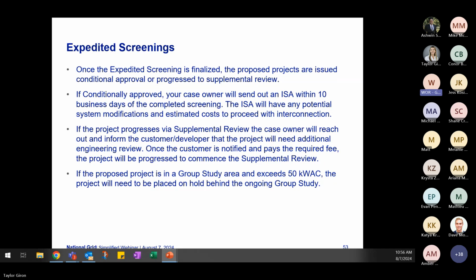Once the expedited screening is finalized, proposed projects are issued conditional approval or progressed to supplemental review. If conditionally approved, your case owner will send out an ISA within 10 business days of the completed screening, including any potential system modifications and estimated costs to proceed with interconnection. If the project progresses via supplemental review, the case owner will inform the customer and developer that additional engineering review is needed. Once the customer is notified and pays the required fee, the project proceeds via supplemental review. If the proposed project is in a group study area and exceeds 50 kWAC, it will need to be placed on hold behind the ongoing group study.